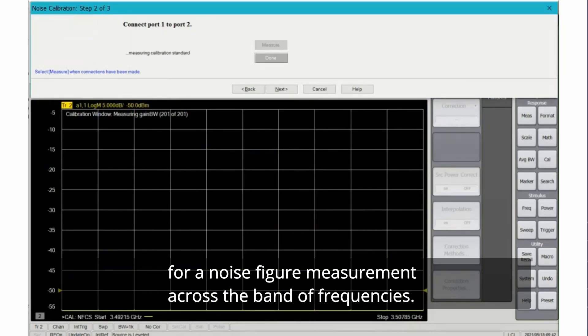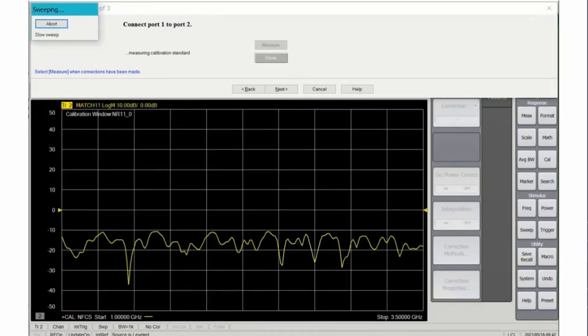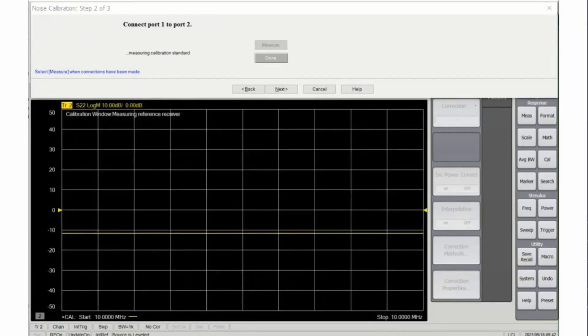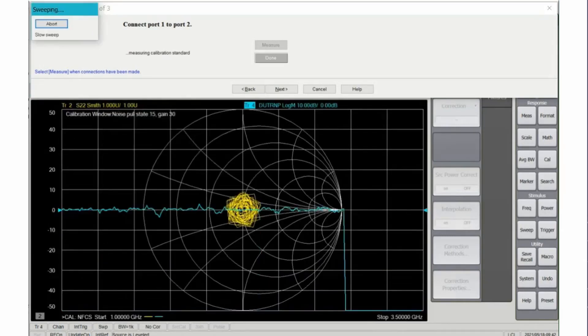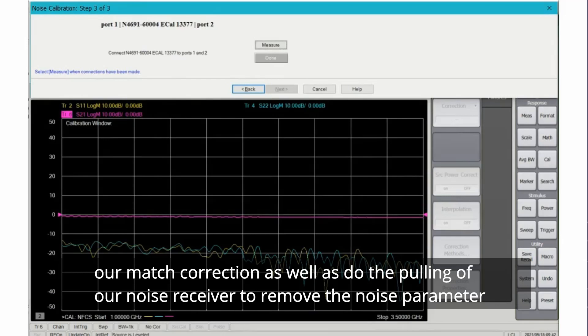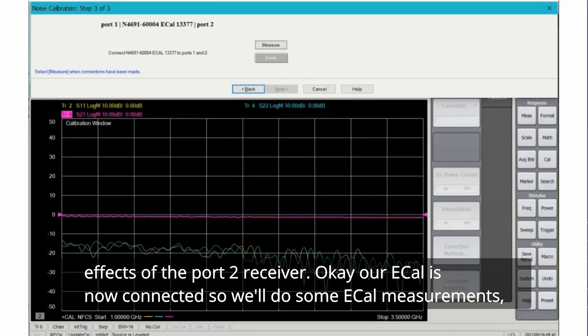During this final step we're going to take the ECAL and put it between the ports and this will do our match correction as well as do the pulling of our noise receiver to remove the noise parameter effects of the port 2 receiver.